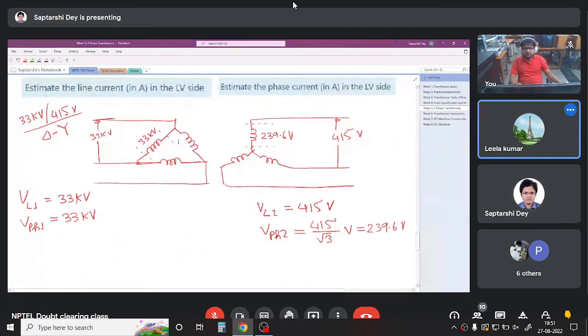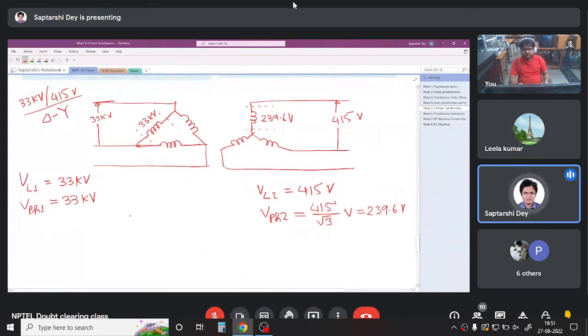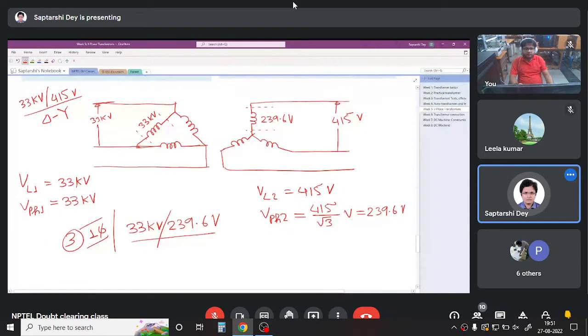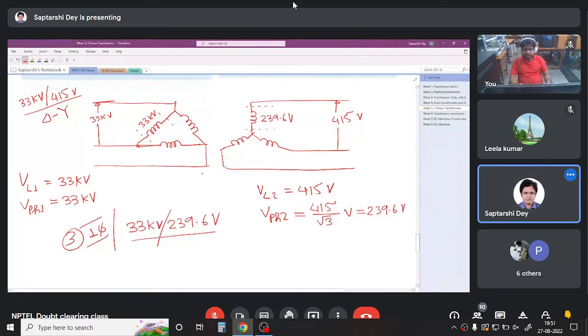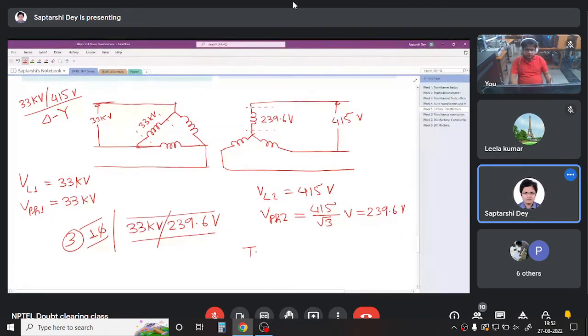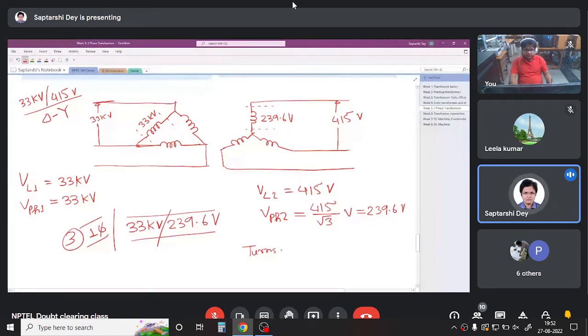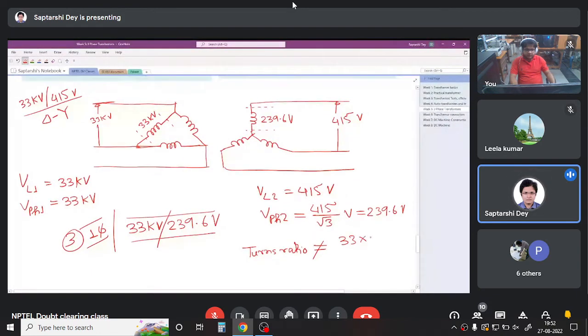Okay. So basically, if I want to realize this three-phase transformer with 3 units of single-phase transformer, I have to take single-phase transformers that are rated for 33 kV by 239.6 volt, right? Not 33 kV by 415 volt transformers. I will end up getting over voltage on the secondary side. So I have to take 3 single phase transformers of this voltage rating, and then connect them in this fashion so as to get this rating. In other words, what is the turns ratio? The turns ratio is not equal to 33 kV by 415.